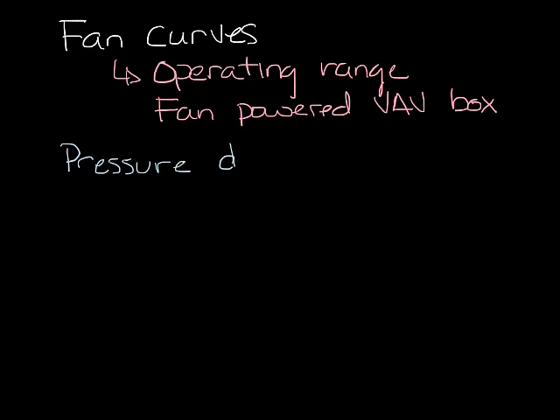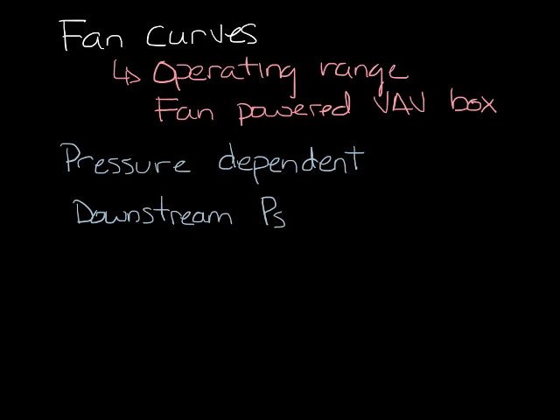Fans are pressure dependent. This means that their performance depends on what pressures they operate against called the downstream static pressure. In other words, the airflow, the CFM, is dependent on the static pressure that they're working against. In general, the higher the pressure the lower the CFM.